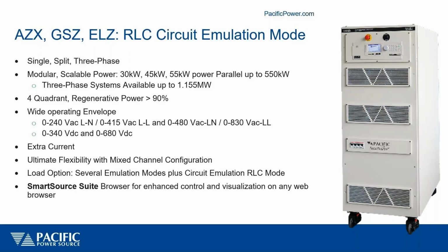It has overcurrent capability for short periods of time to ride through inrush currents, and the ability to not only run single, split, and three-phase, but also combine multiple channels. So if you had a single-phase DER, you could use one channel for a grid simulator and a second channel for the electronic RLC load. So you could do a test setup with a single unit. So very flexible in that sense.